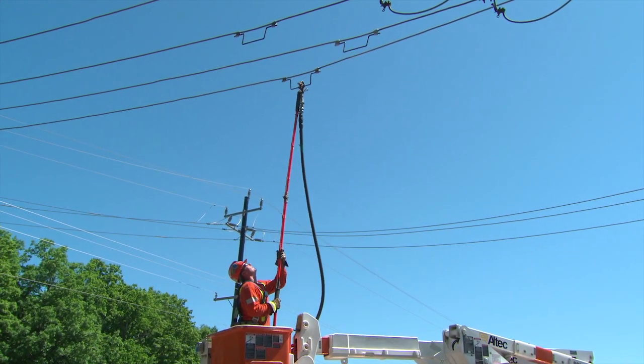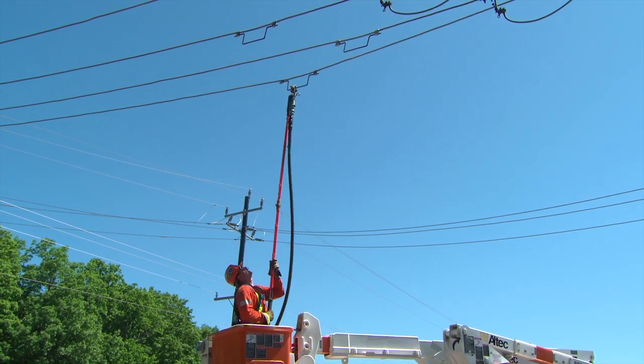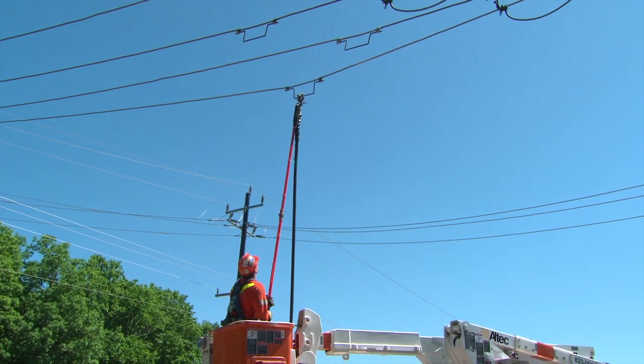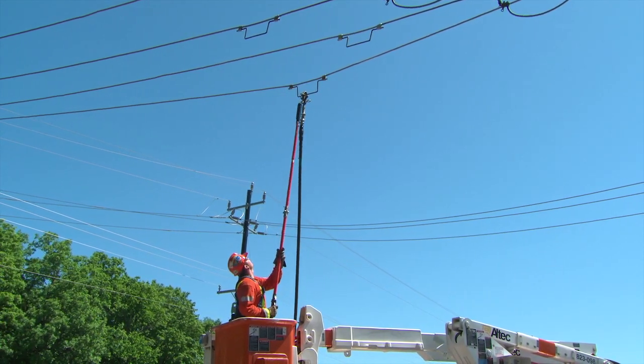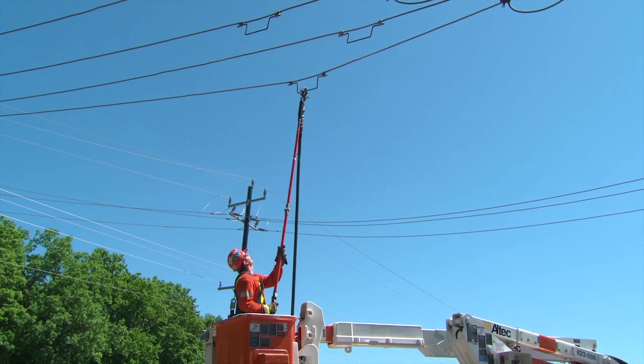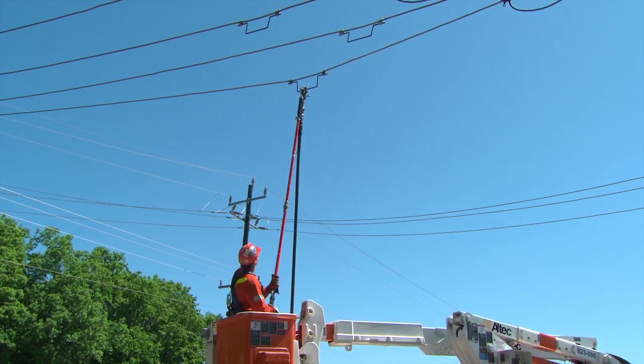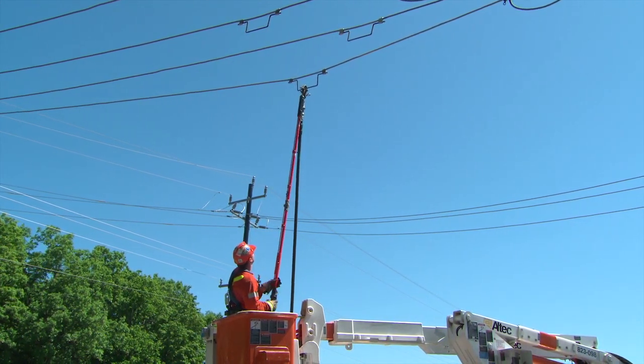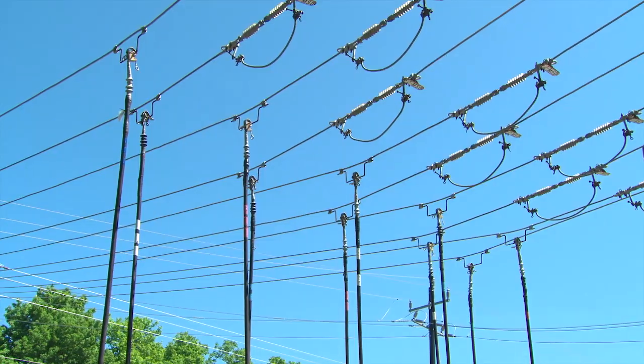Connect the neutral cable to the corresponding DS neutral position and then connect the MUS low voltage cables to the energized DS low voltage feeder stirrups. Because the DS feeders exit overhead at this station, a bucket truck is required to hang the MUS feeder cables.